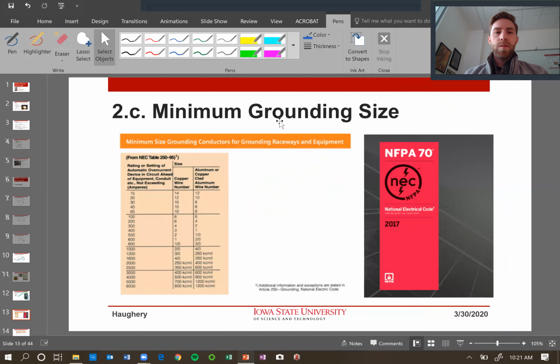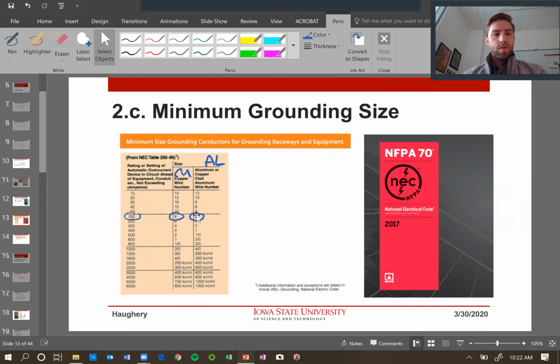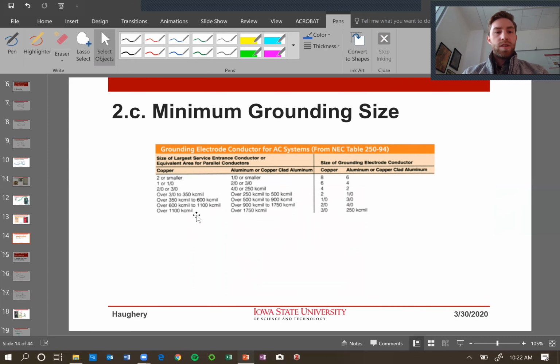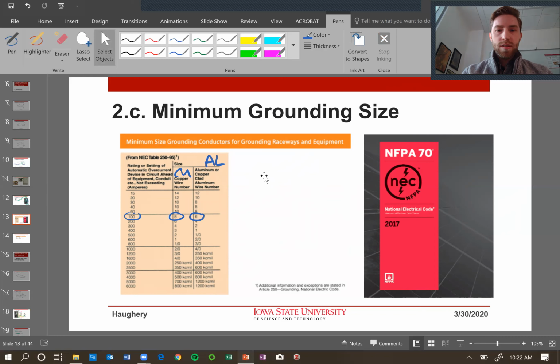If we look at the minimum grounding conductor sizes, we have a copper column and then we have an aluminum column. If we notice here, the gauge for our aluminum is always going to be slightly larger because the conductance of aluminum is not quite as good as copper. And so based on the rating of our circuit breaker, if we have a 100 amp circuit breaker, we would use an 8 gauge copper or a 6 gauge aluminum. Similar with, so this is our system grounding. Oh, this would be equipment grounding. Okay, so this is our equipment grounding conductor sizes.